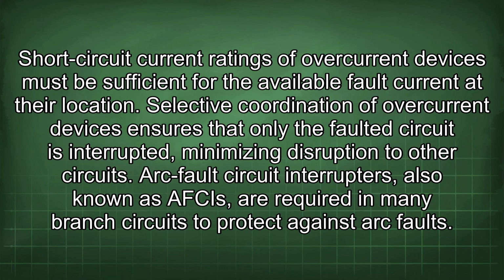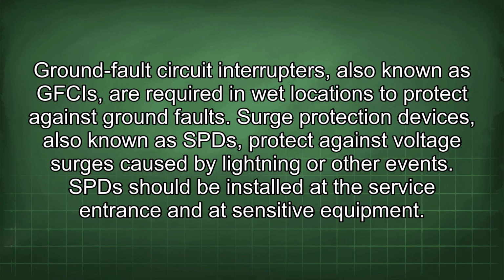Short circuit current ratings of overcurrent devices must be sufficient for the available fault current at their location. Selective coordination of overcurrent devices ensures that only the faulted circuit is interrupted, minimizing disruption to other circuits. Arc fault circuit interrupters, also known as AFCIs, are required in many branch circuits to protect against arc faults. Ground fault circuit interrupters, also known as GFCIs, are required in wet locations to protect against ground faults. Surge protection devices, also known as SPDs, protect against voltage surges caused by lightning or other events. SPDs should be installed at the service entrance and at sensitive equipment.